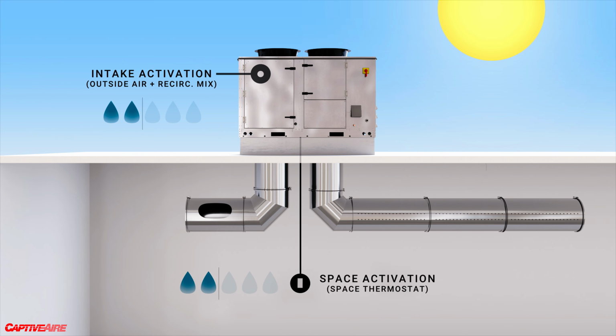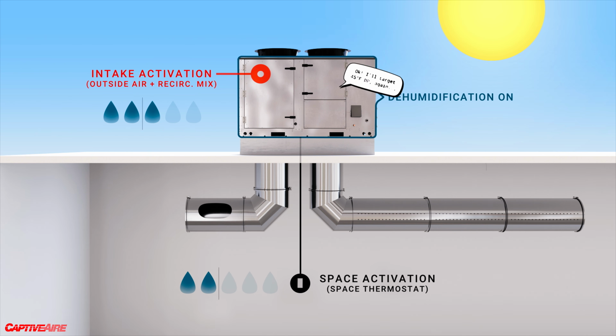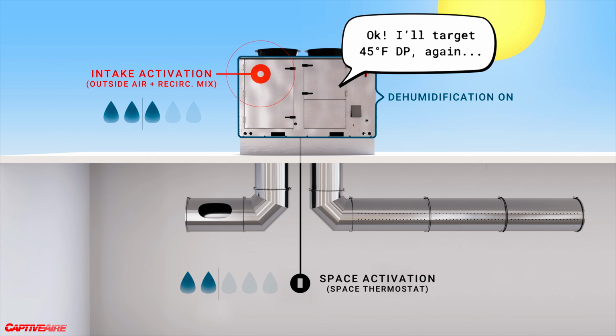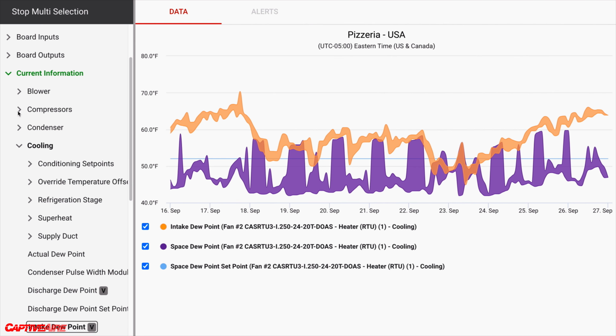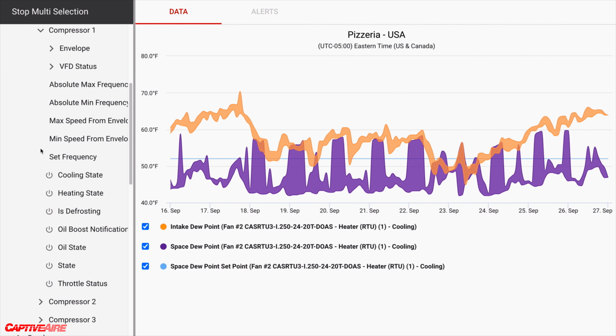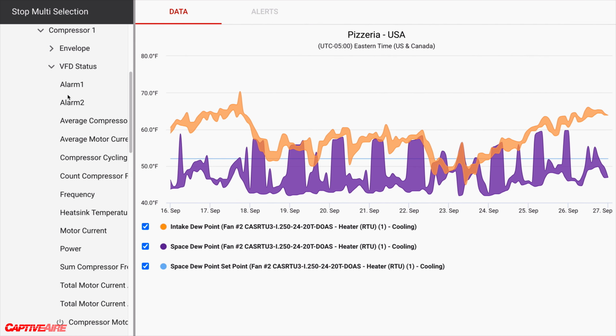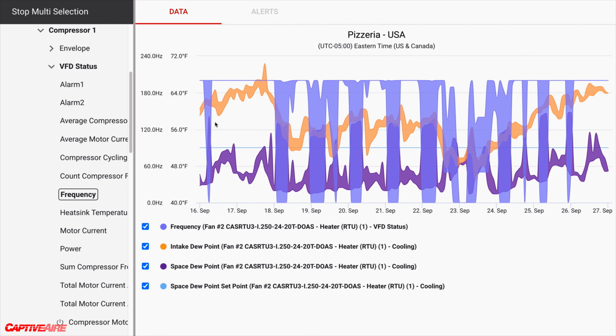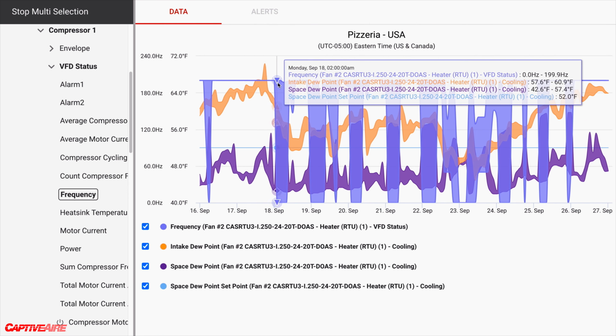But any other day that is not that peak design day, if you activate because of intake, you're going to be over dehumidifying and that space will be below your dew point. But as long as the humidity is high enough to keep that intake activated, you're just going to keep dehumidifying that space further and further. And you result in a situation like this where now our compressor, if I plot my compressor speeds in here, we might be running at 3/4 load where we could have been running at half load on that compressor. We'll pull it up and actually take a look. We're running at full compressor speed much of the time here, 200 hertz.